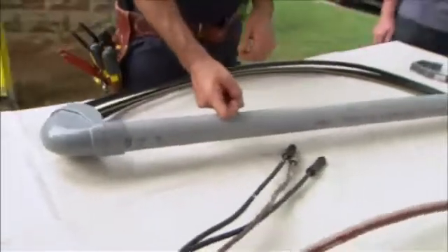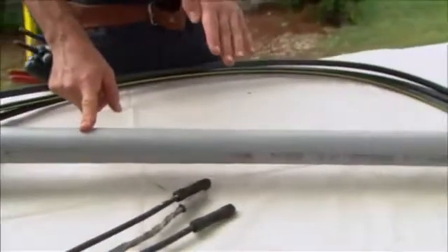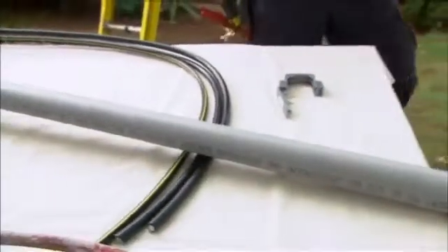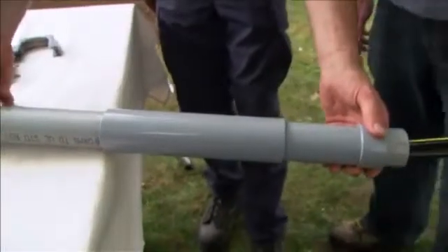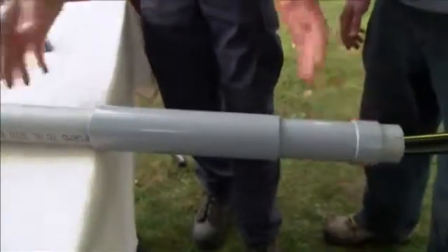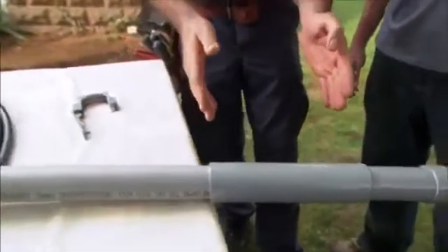And now we have this really rigid PVC conduit, which offers the wires inside a lot more protection. However, it expands and contracts with temperature change, so we have to do a couple things. We add this expansion coupling right here, which allows the pipe to expand and contract with the heat.